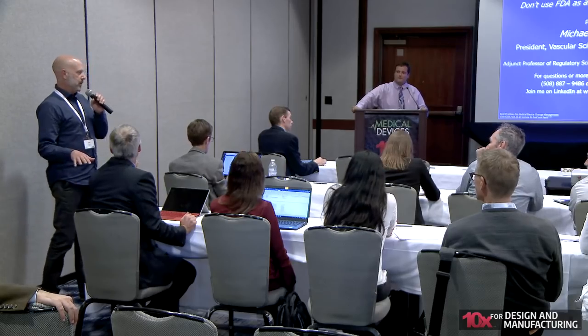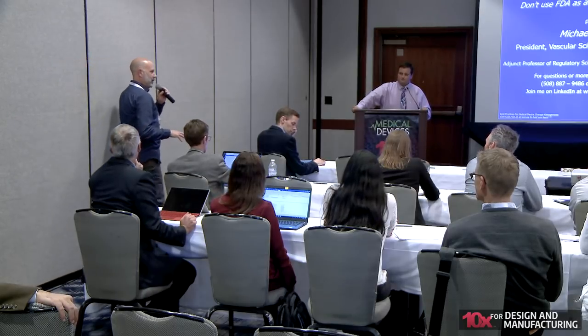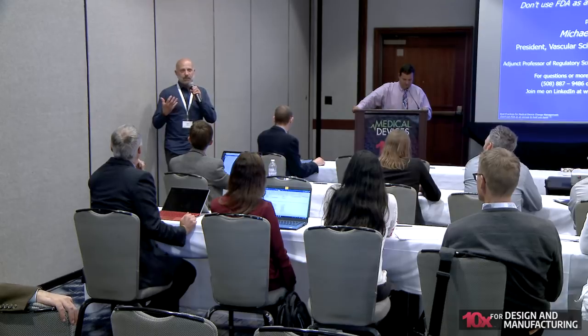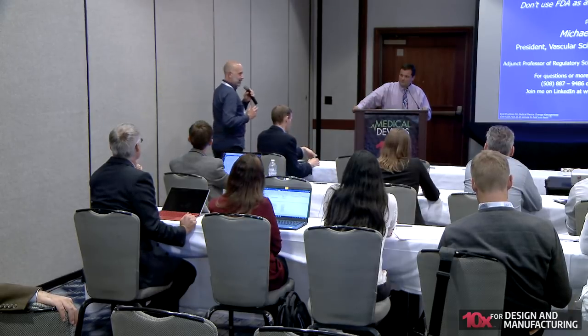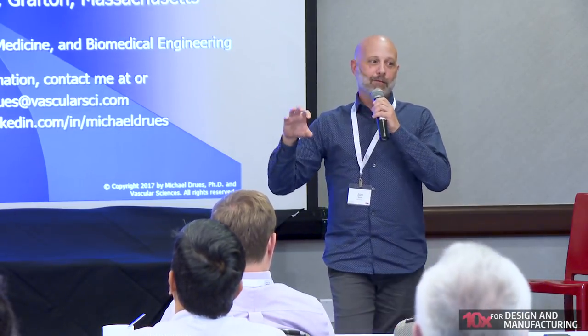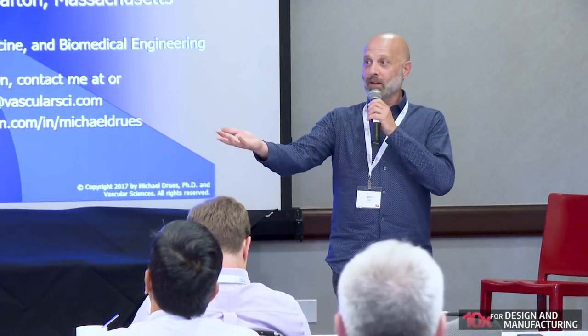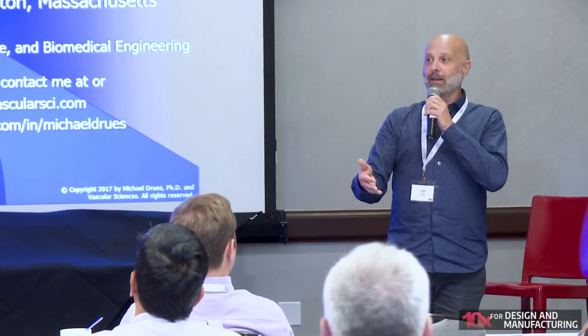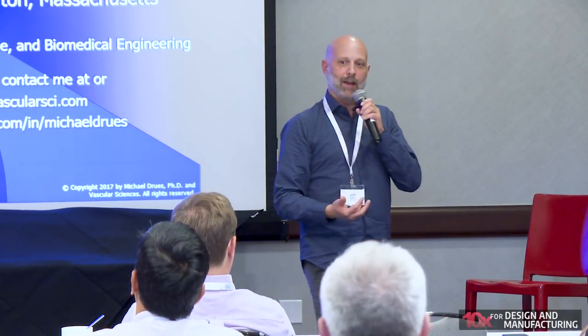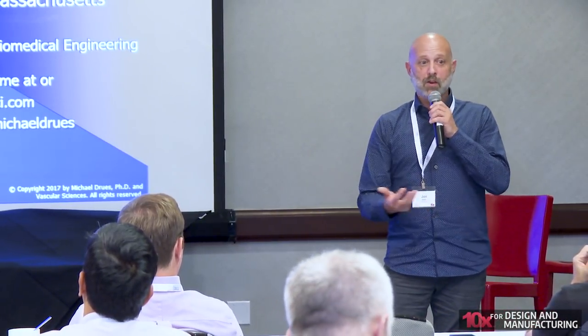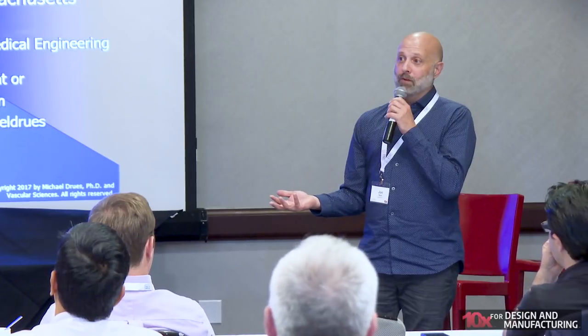Well, I would build on what Scott was offering, because in my experience, what happens during the design and development process, the product development team does usually a pretty decent job of documenting design controls and risk management activities. And the moment that design transfer happens, that file gets archived and buried. And those are not the people who will continue to maintain that product once it's in the manufacturing environment. Now you have a sustaining team or a manufacturing team, some other group who did not design and develop the product, whose responsibility is to author these changes. And they're making changes blindly because that design history file, that risk management file, oftentimes is buried somewhere in archive. And they don't go back to that design history file, those design controls, to see if the change they're making has any impact upstream or downstream to the decisions that were made when that product was originally launched.